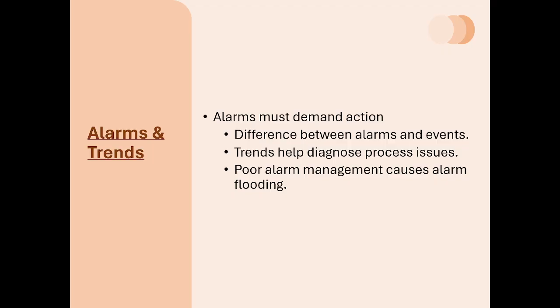Let's clearly define these two terms. An alarm is not just any warning, it is a condition that requires immediate operator action. And a trend is a graphical display that shows how a process value like pressure or temperature changes over time. Trends help operators see problems developing before alarms even occur. And if alarms are too many or poorly prioritized, operators become overwhelmed. And this is why alarm management follows specific standards.